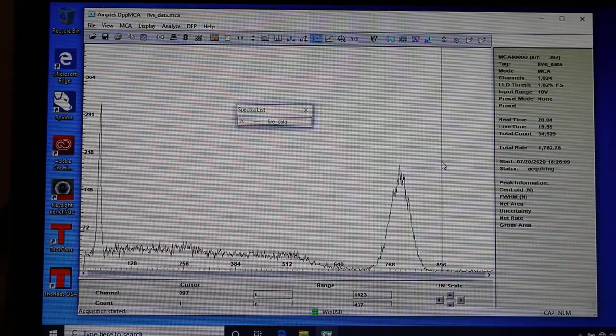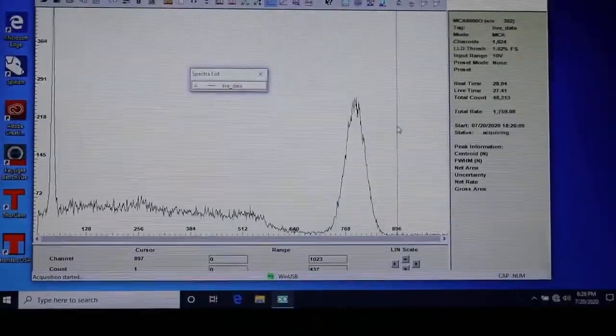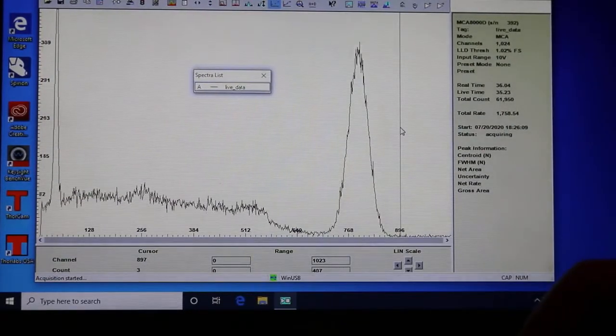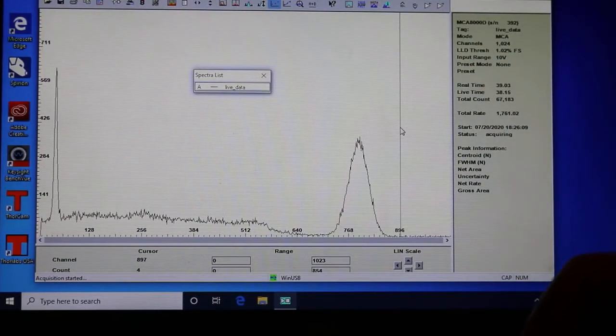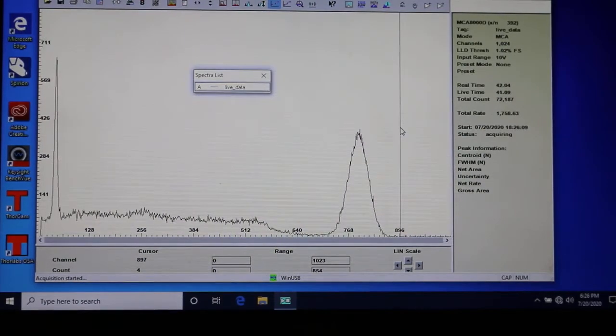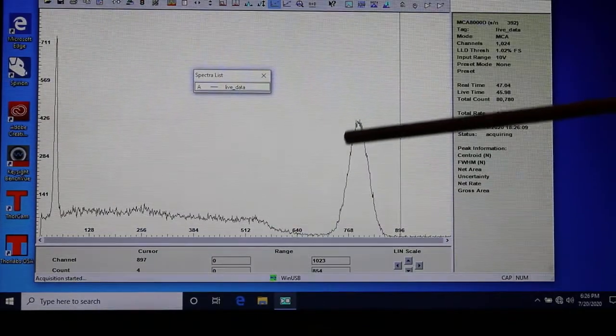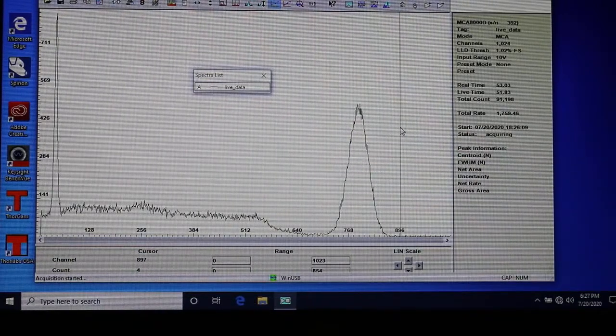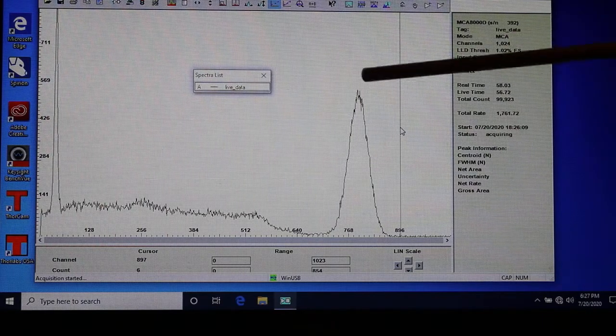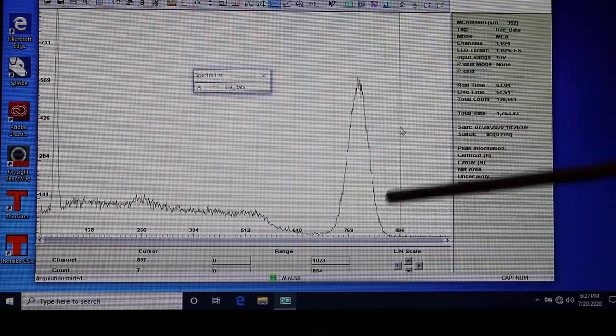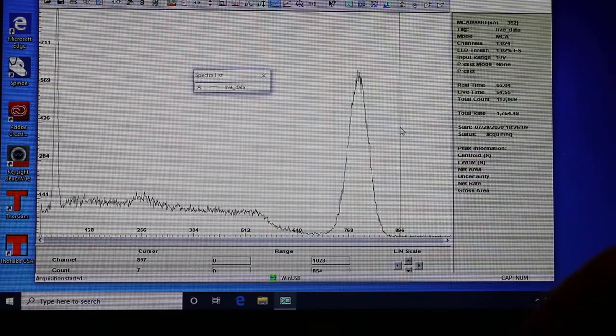So you can see these voltages which appear to cover all cases here obviously do not. They do not cover all cases right here. You don't see these channels growing uniformly all the way across, so all voltages are not represented equally as this spectrum comes in. But what do you see? This is Cs-137, a very famous and characteristic spectrum, one of the most common. You see a lot of energies coming in right here under this peak. Most of them are coming in under this peak right here. And Cs-137 is a mono-energetic gamma ray emitter. It emits a 663 keV gamma ray. So maybe the clutch of all these gamma rays here with a little bit of spread in the detector could be all of those 663 keV gamma rays coming in. Indeed they are it turns out.